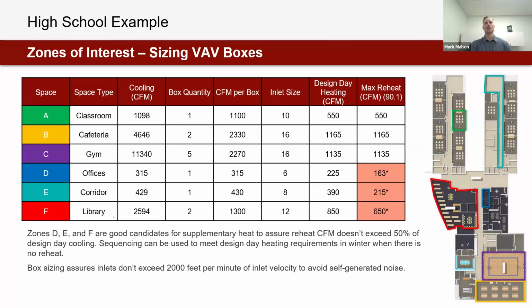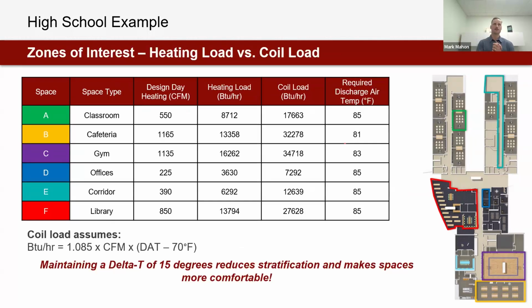And we can kind of see the process here where I've sized the inlets, I've sized the design day heating CFM requirement, the cooling CFM requirement. And I also want to note, in some cases, the design day heating CFM for this little energy model actually had CFMs exceeding 50% of design day cooling. So in some cases here, that would need to be addressed via sequencing. There'd maybe be a need for some supplementary heat in the zone if we don't want to do full heat through the VAV system, but another consideration to flag there.